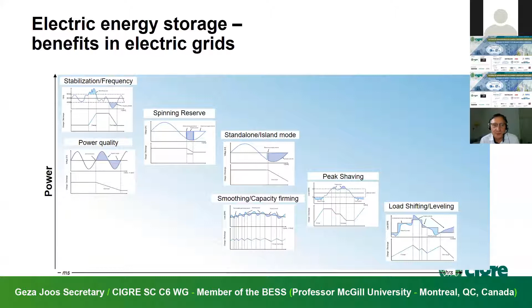So here are examples of what the battery can provide in terms of benefit. This is typical of an islanded system that runs a diesel generator and has solar panels. The battery essentially smooths out the diesel power, allowing the load to be met with a combination of variable PV power and a diesel engine that tries to run at constant speed. In the middle of the slide, the diesel is turned off and the system runs from a combination of PV and afterwards a battery. The PV power is very large midday, enough to not only feed the load but also recharge the battery.